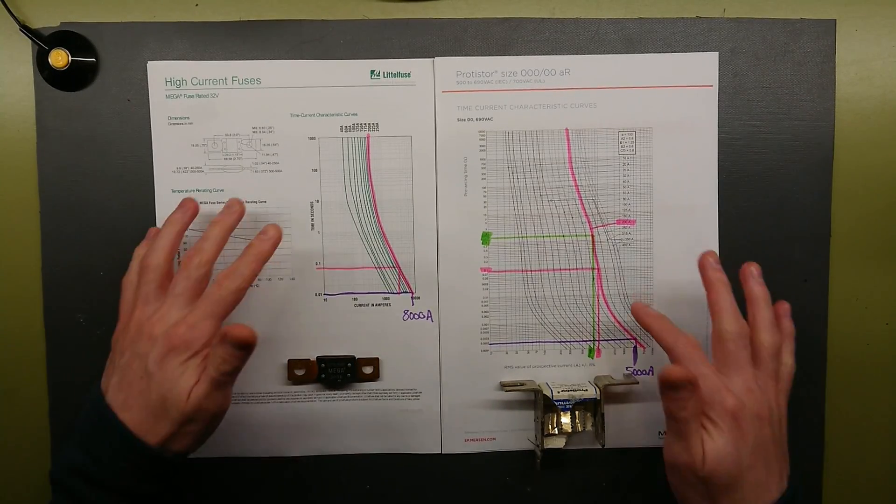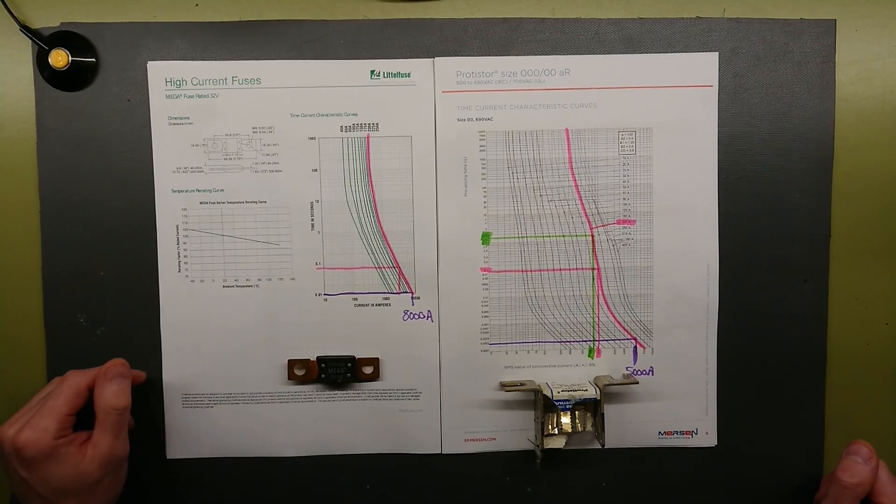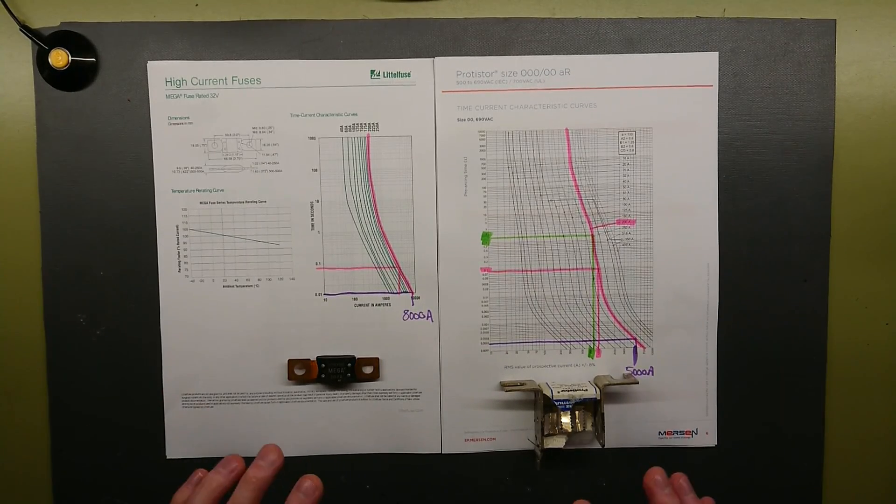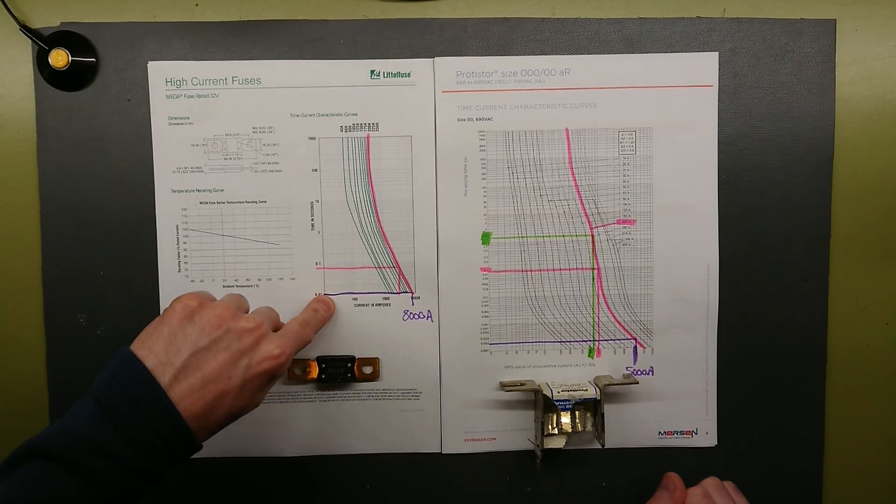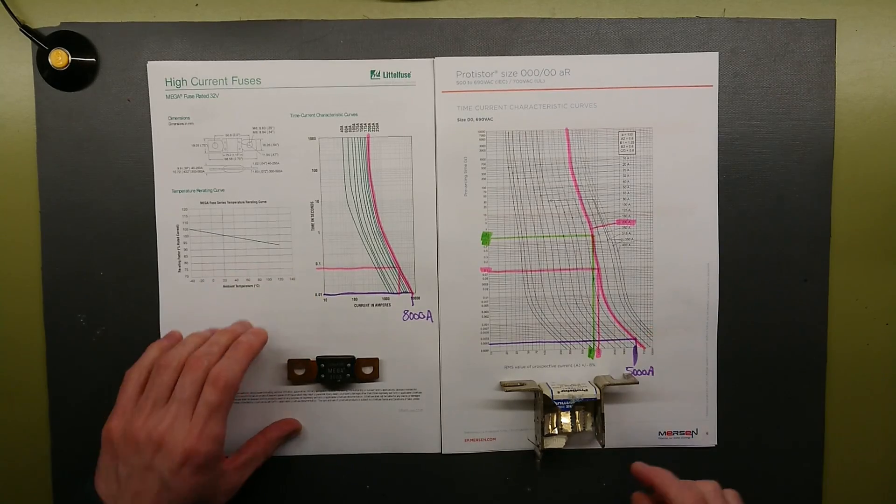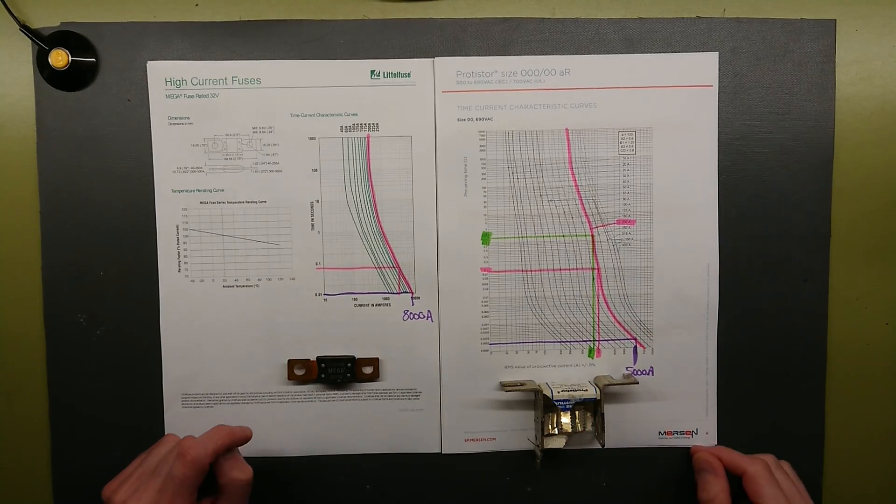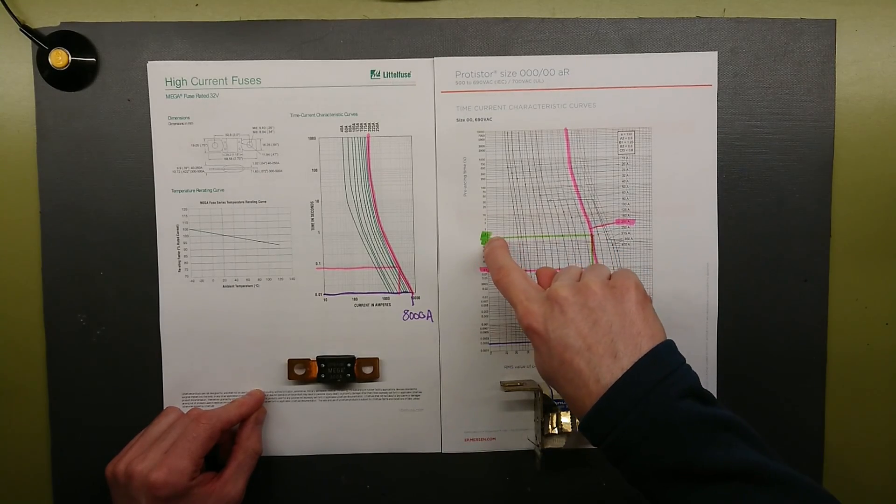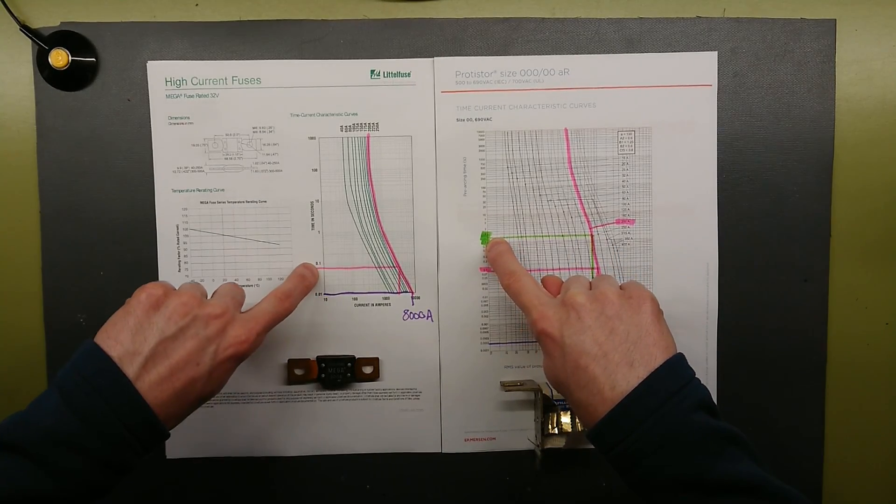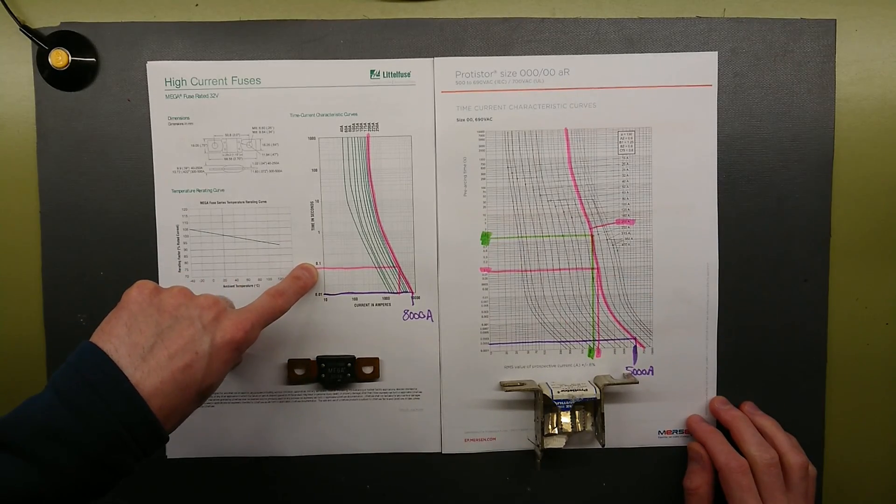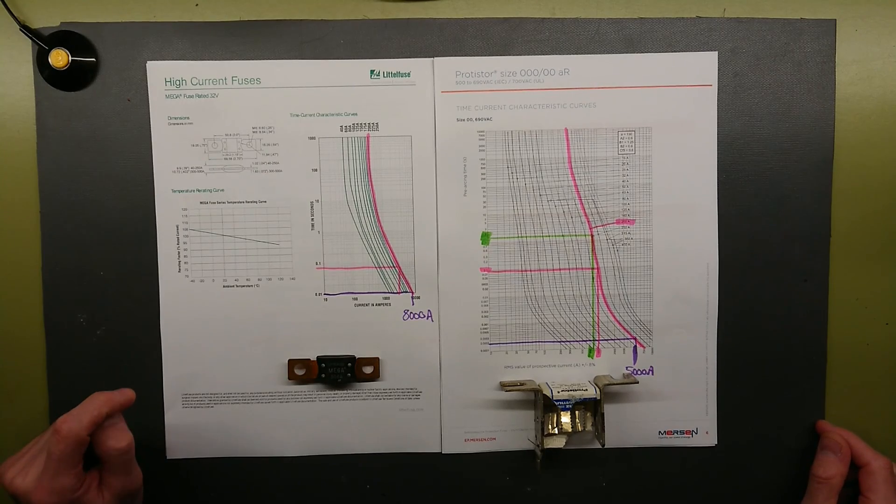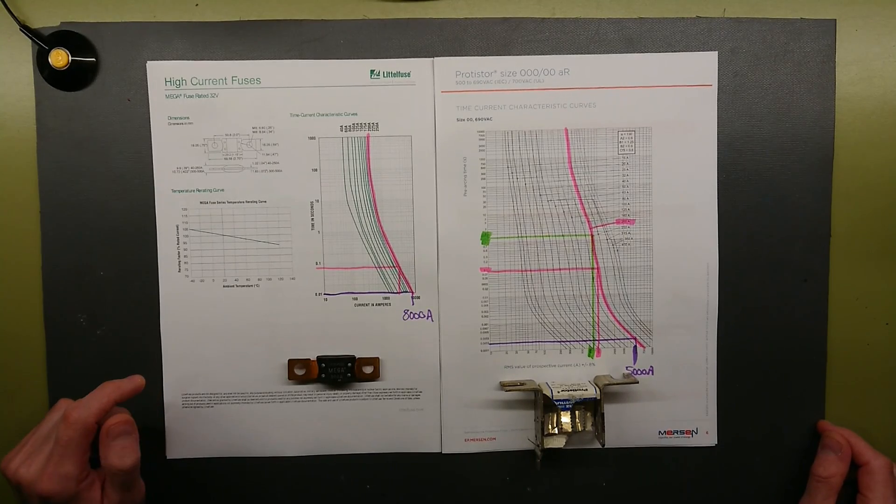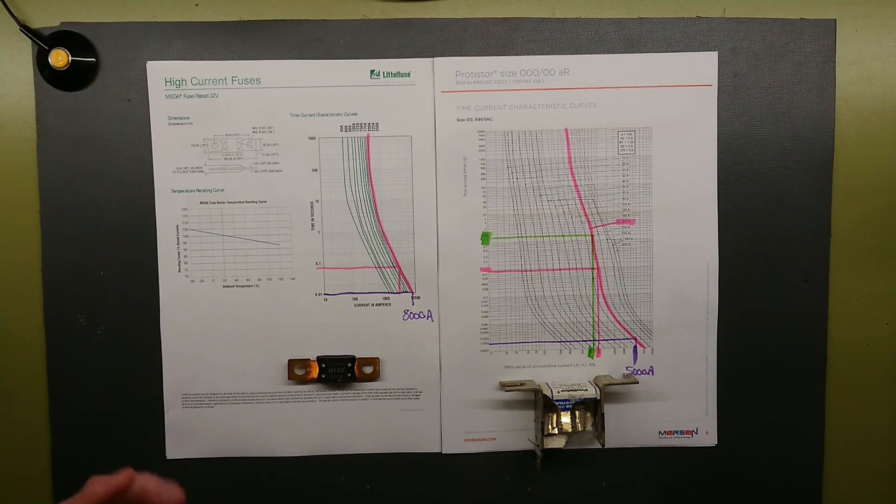I marked up some parts of the characteristic curves here. If we look at 4 times the current that these are rated for, 1200 amperes for the 300 unit and 800 amperes for the 200 ampere unit. This would melt out at 1.5 seconds where this would melt at 0.08 seconds or 80 milliseconds.